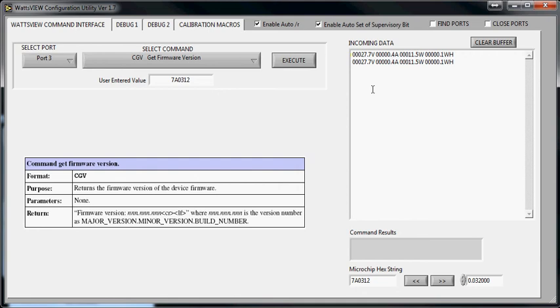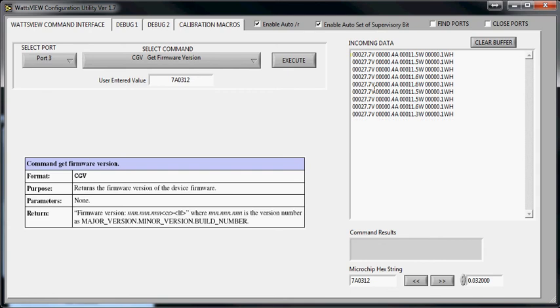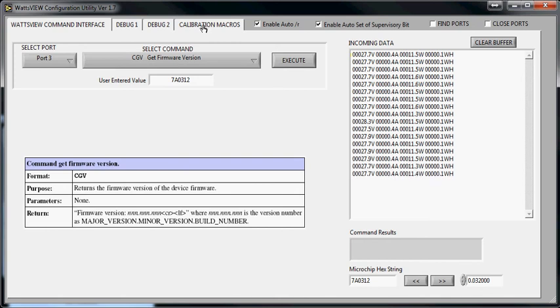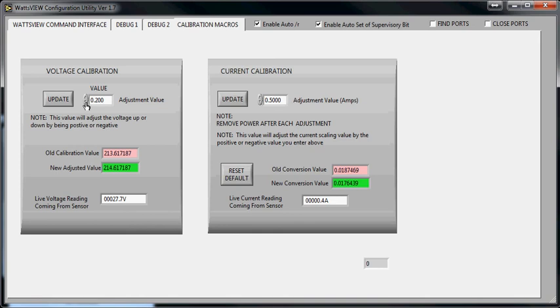Right now we're reading 27.7. If we know that our power supply is calibrated and very accurate, and we want the 28.3 value to show up, then you click on this tab that says Calibration Macros. You go over to the voltage, and here's the reading coming in right now. It's 27.7, and we want 28.3, so that's a difference of about 0.6.